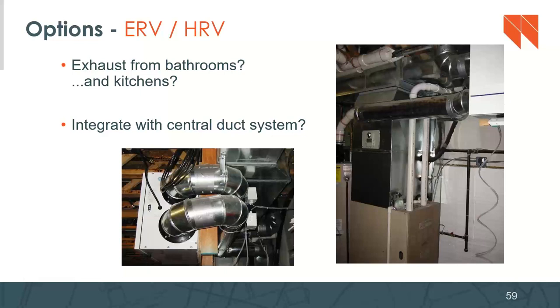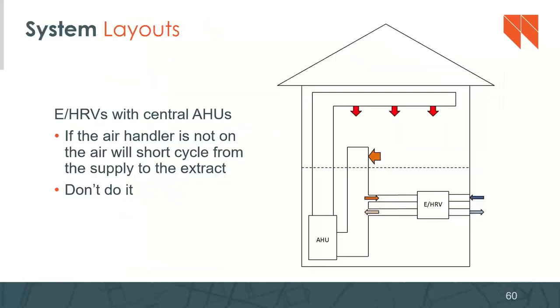You could integrate it with exhaust air from the bathrooms and the kitchens. You could integrate it with a central duct system. That's what these photos are depicting. Let's see this in a layout that's a little easier for us to talk about. E/HRVs with central air handlers. So you can see the ERV or the HRV, whatever your recovery ventilator is, both the stale air going out of the building and the fresh air coming into the building are, in this example, tied to the return side of the air handler.